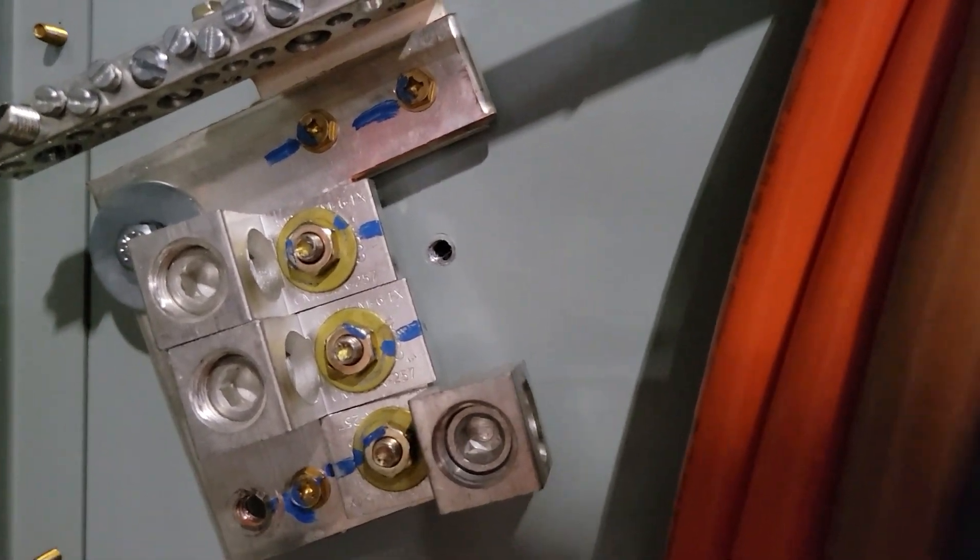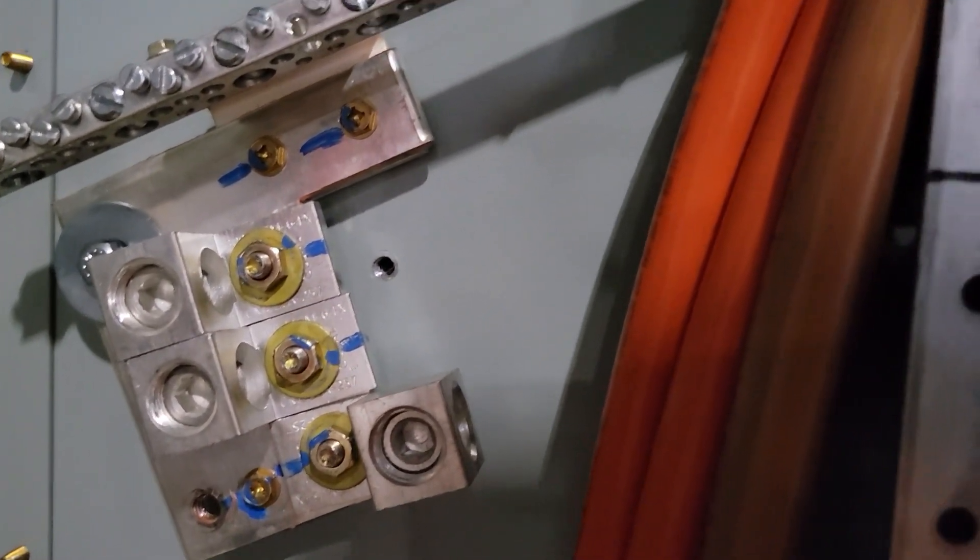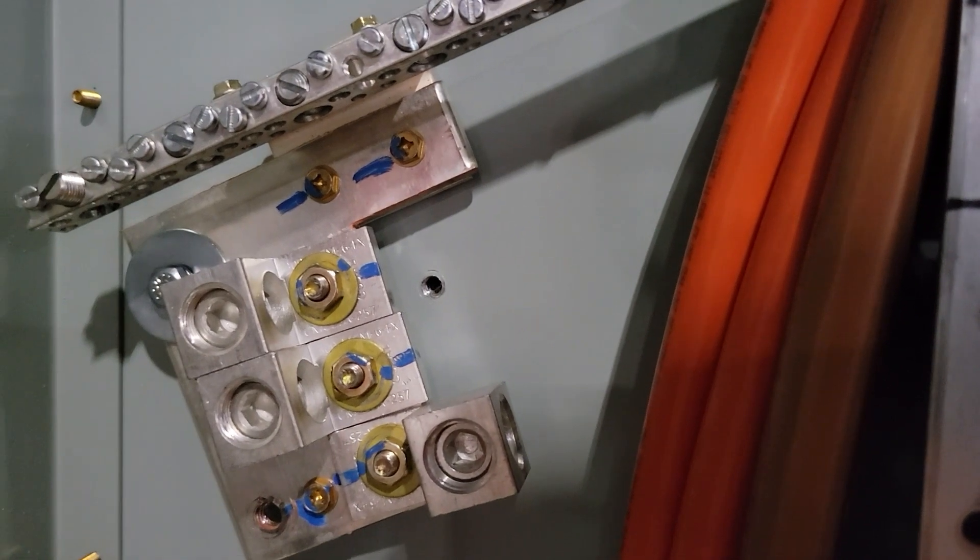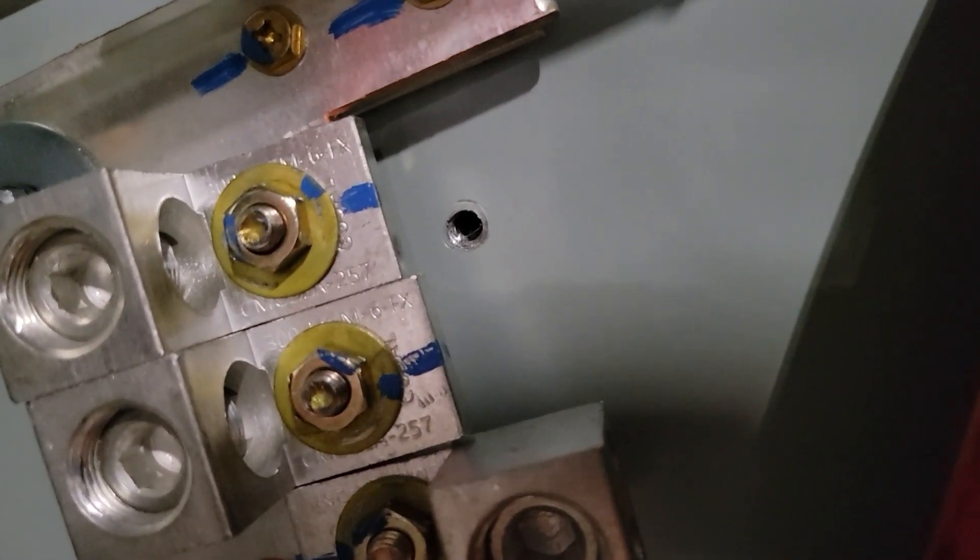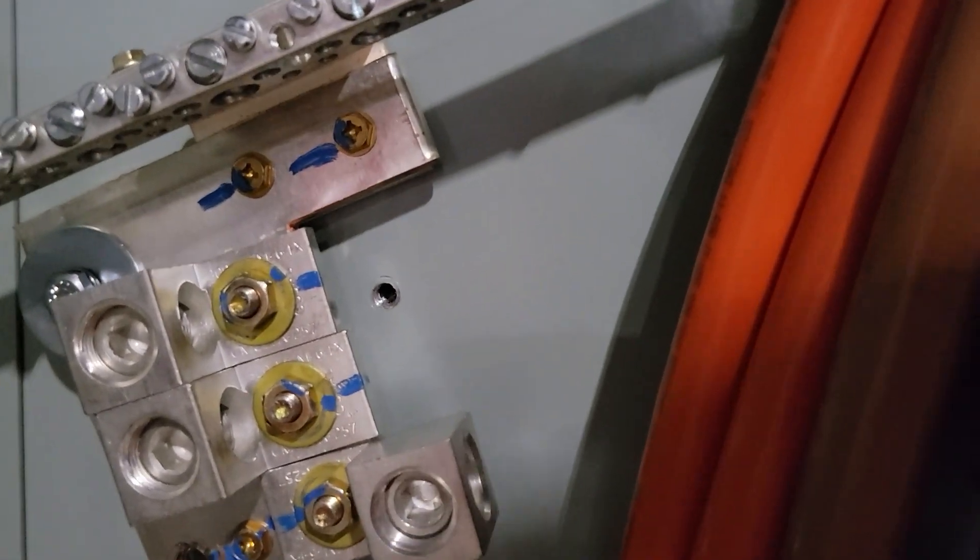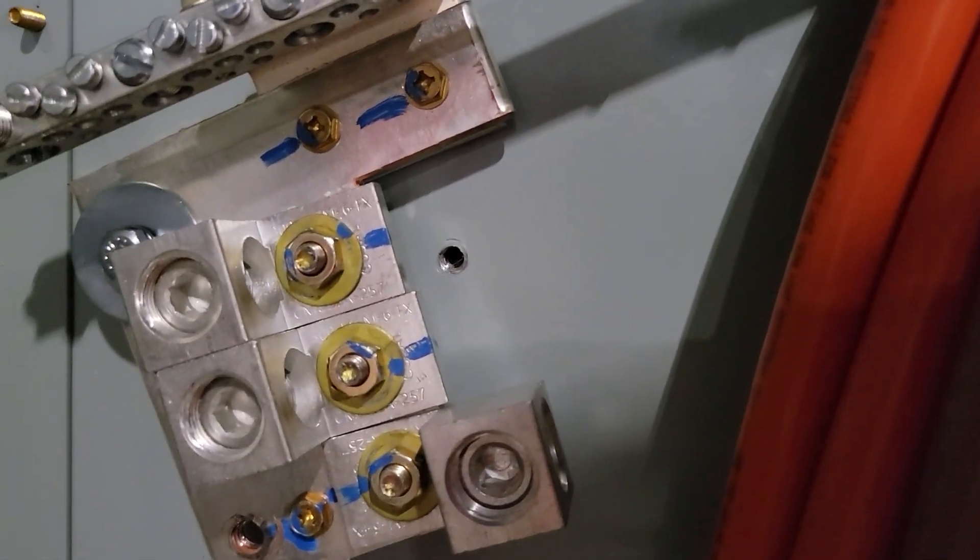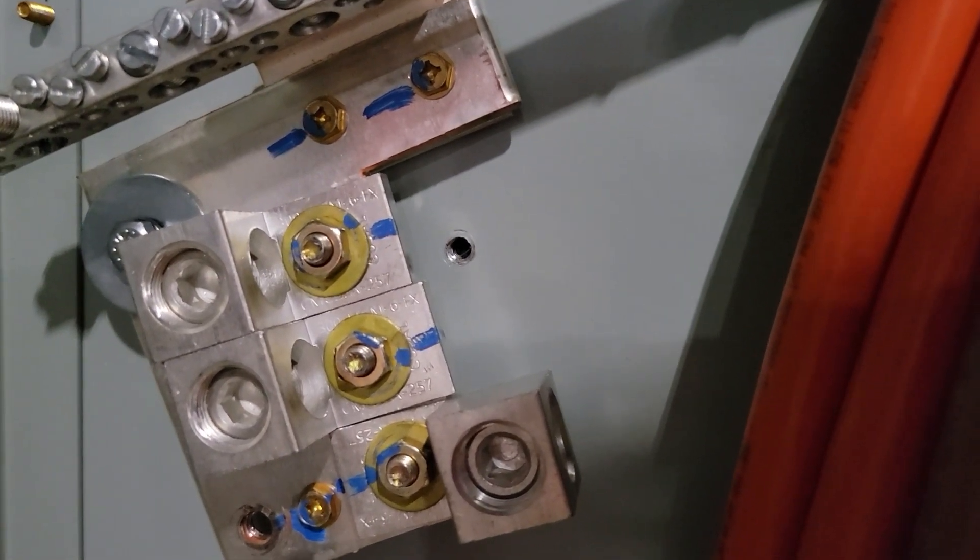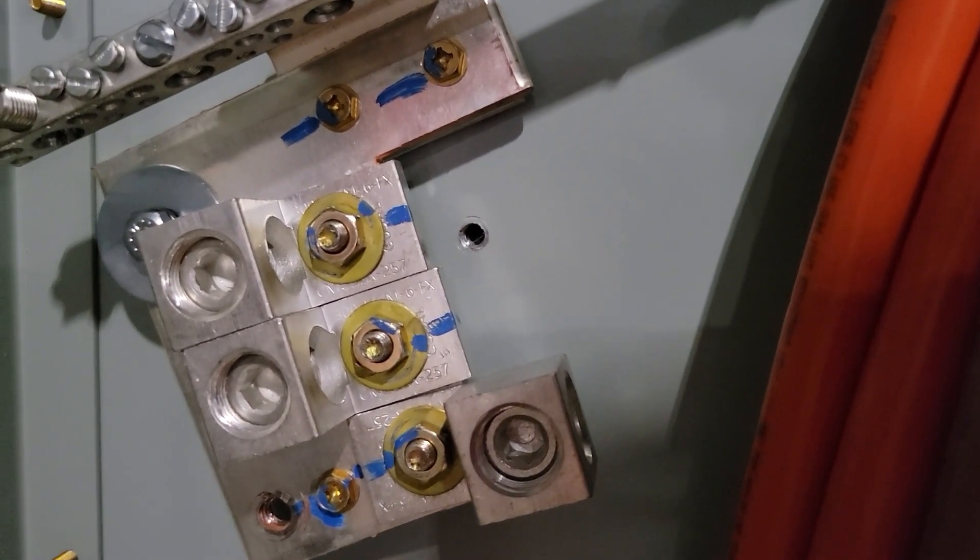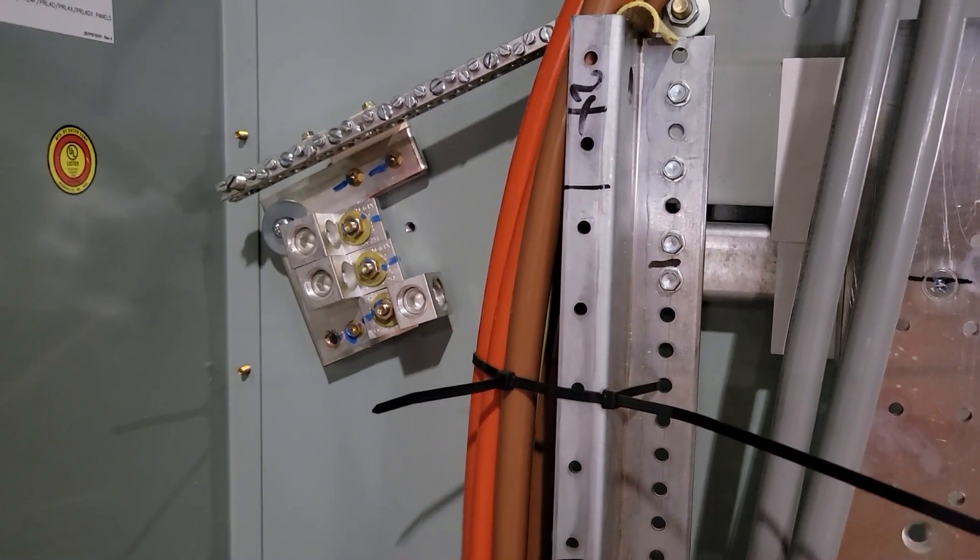sure you have a threaded hole and do not use machine screws. It is against the NEC code, and if you've got a good inspector, they will fail you for it.